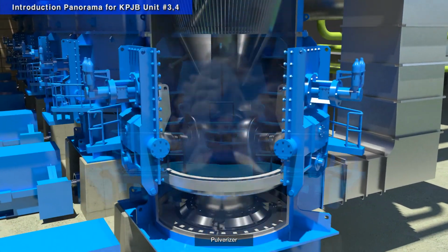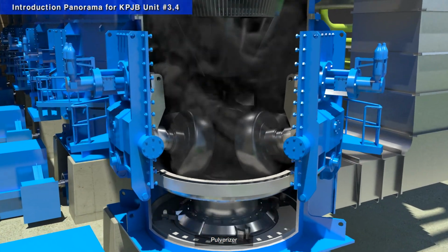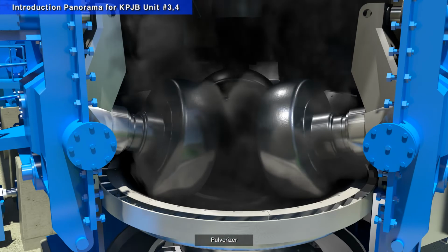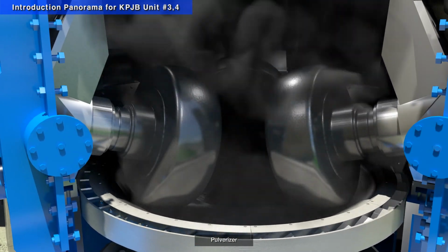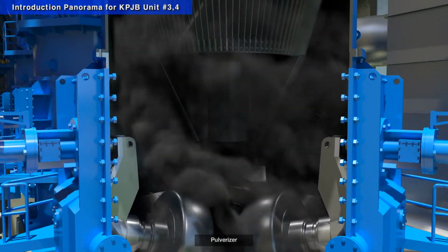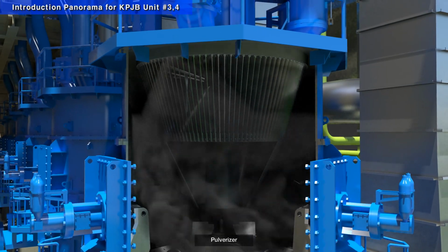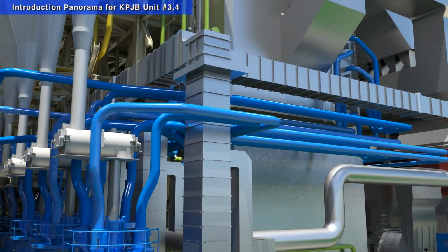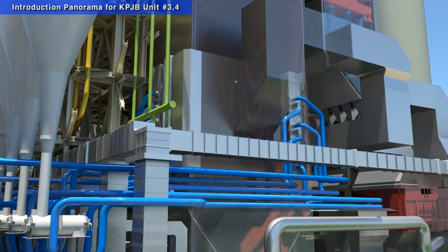The pulverized coal, which has been crushed from the pulverizer, will be burned after being input into the center of the boiler through the coal nozzle of the wind box after going through 4 coal supply pipes, with preheated air at the regenerative air preheater.